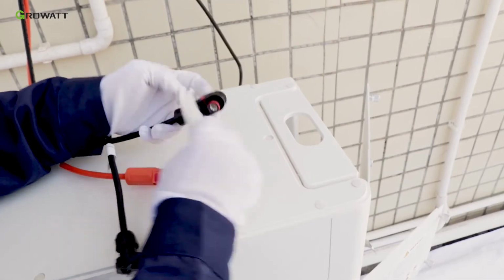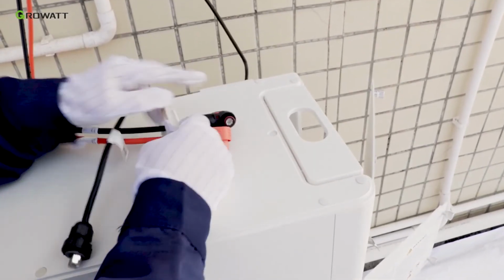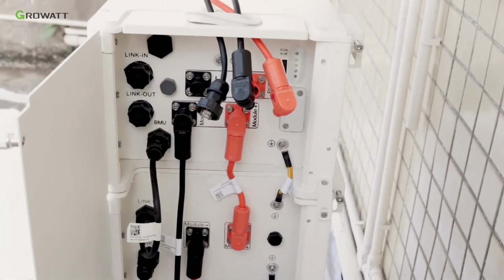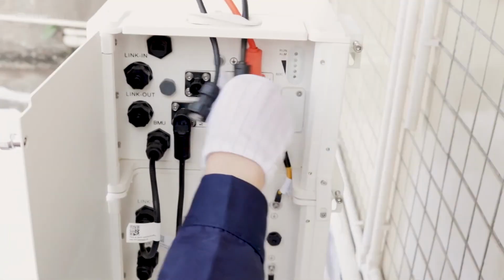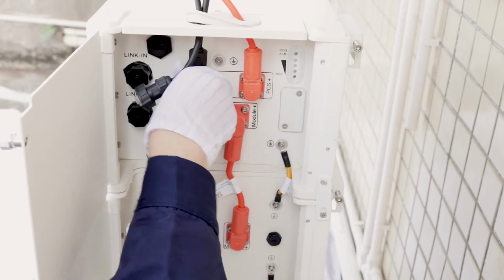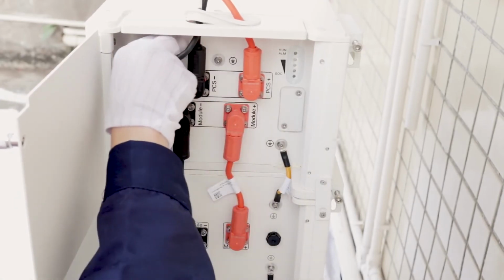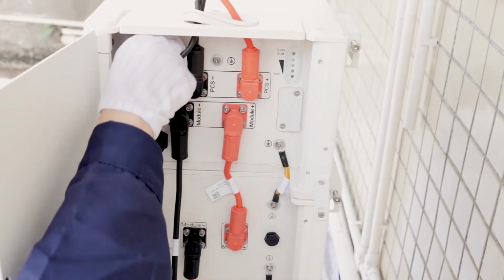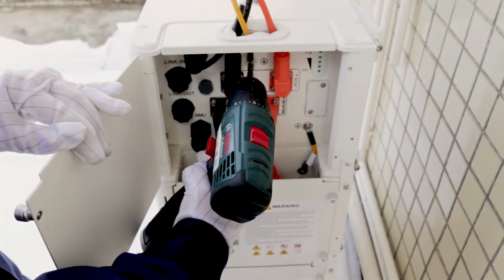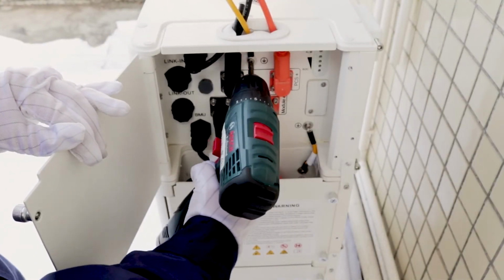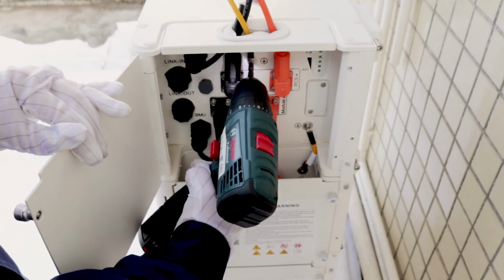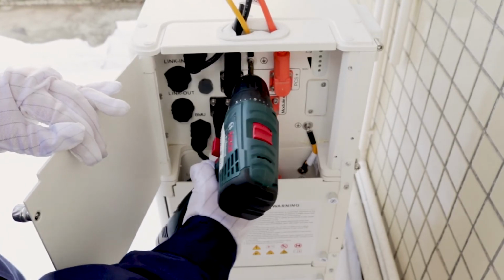Power and communication cables from the hybrid inverter need to go through the rubber cover. Then connect the negative and positive power cable to the corresponding terminals, and connect the communication cable to the PCS port of the BMS module. Please remember to connect the ground cable made by the installer from the whole ARK battery system to the earth point. Finally, close all the mantle covers.